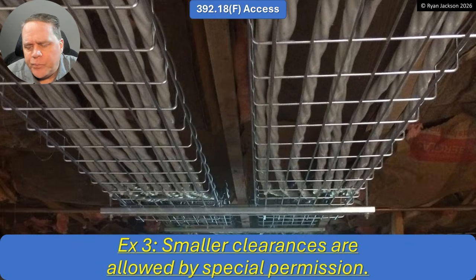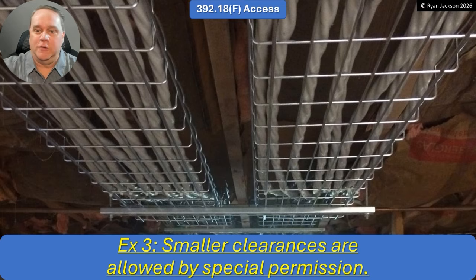Number 3, smaller clearances are allowed by special permission. This is an interesting scenario here. So this is in some apartments, and you can see that we've used SER cable, and we've got a basket-style cable tray to support them. Do we have 12 inches from the top of the tray to the bottom of that structural ceiling? No, it doesn't look like it. I mean, maybe if you count the depth of the floor joist above, if you had to, maybe you could. But, you know, if those are 9.5-inch floor joists, you might not get it.